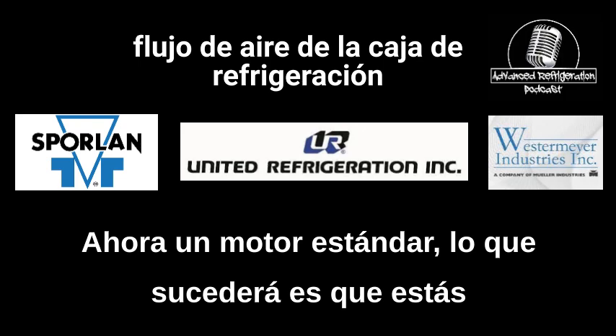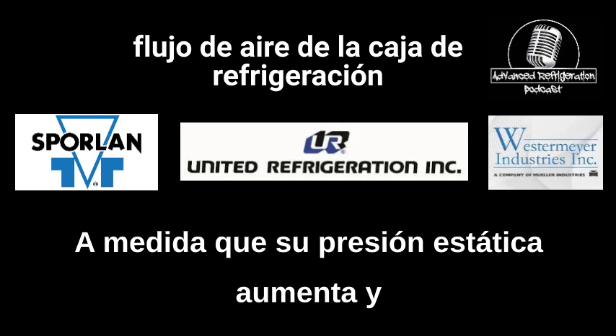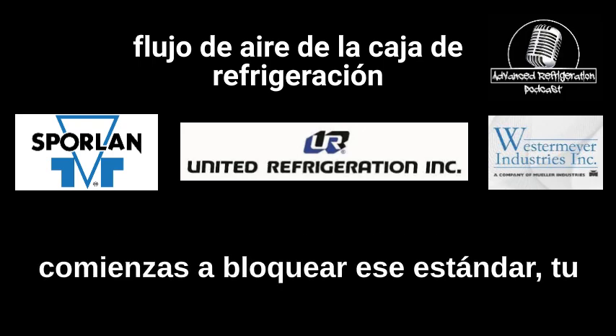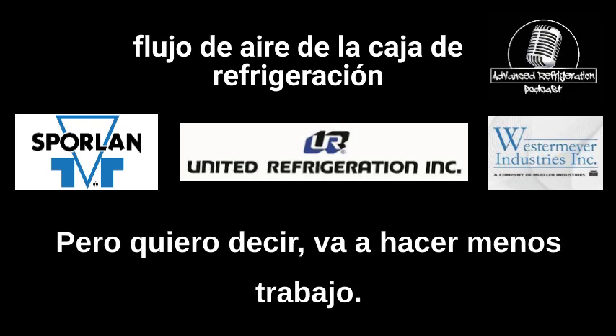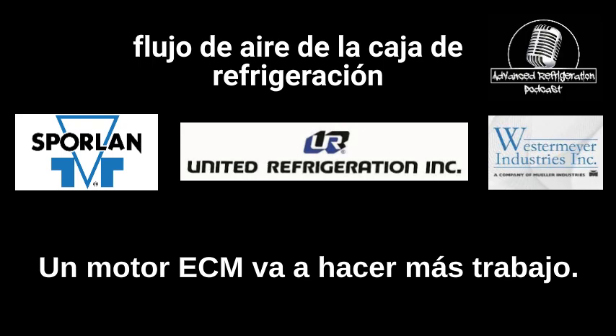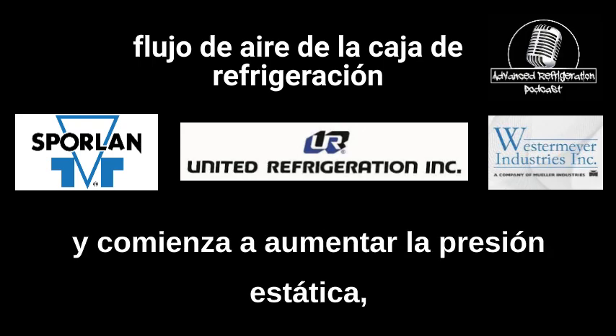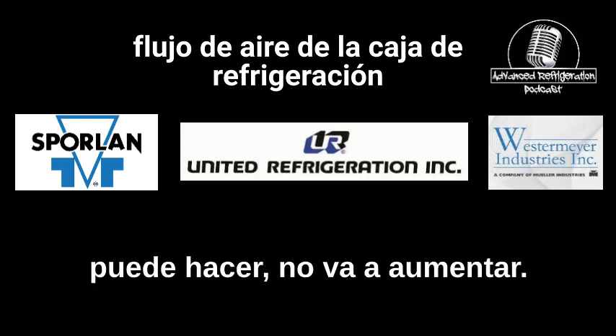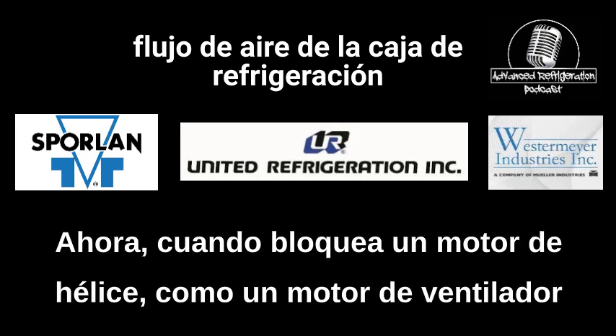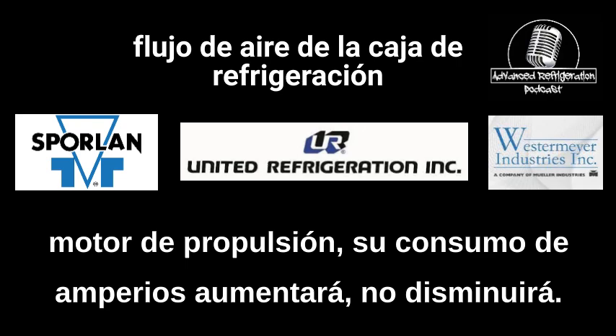Now, with a standard motor, you're going to see your amp draw go down. As your static pressure increases and you start blocking off that standard motor, it's going to do less work. An ECM motor is going to do more work when you start blocking off the airflow and increasing the static pressure. It speeds up to do more work. A standard motor is going to do whatever work it can do. It's not going to increase. Now, when you block a prop motor, like a fan motor in a case or a condenser fan motor, your amp draw is going to increase, not decrease.